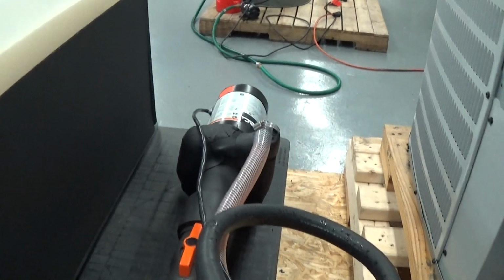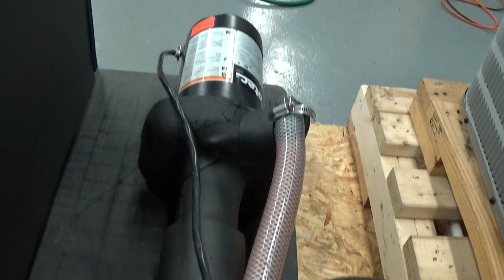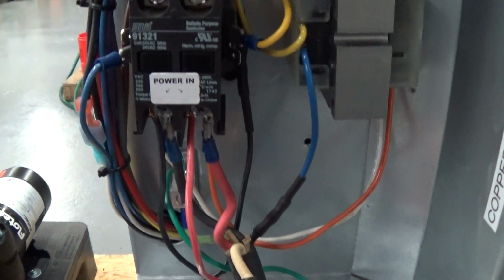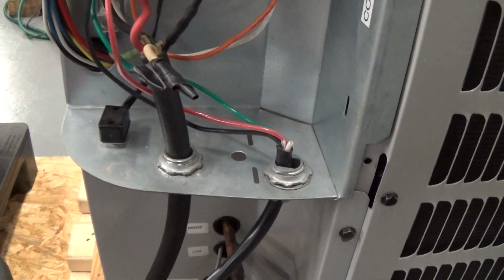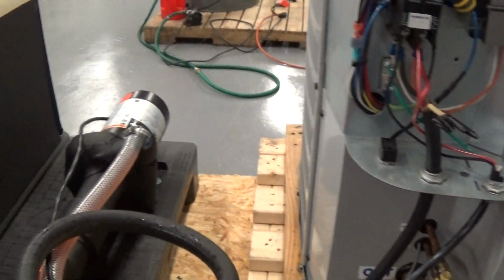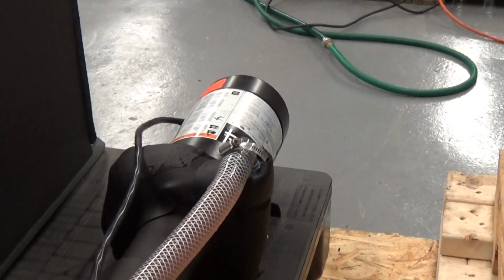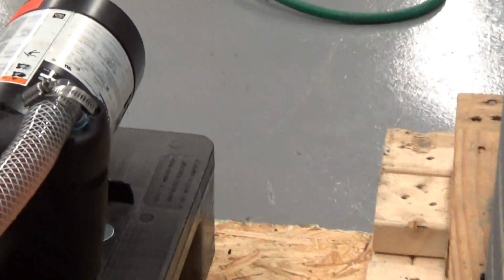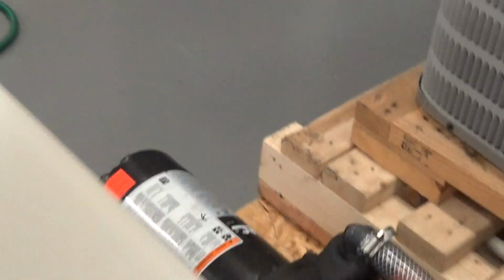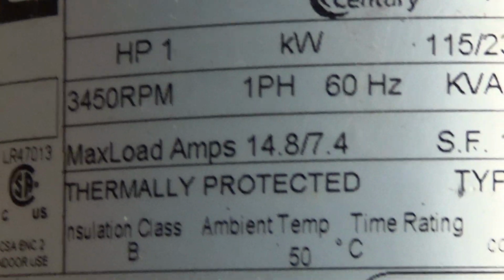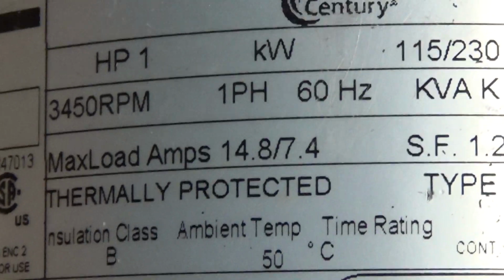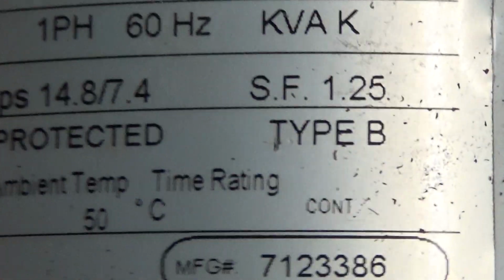The chiller is wired for 208, 230 volt single phase power. In our test environment here, we actually just wired it right back to the main power in here. You can do that too. If you do, just make note of the amp ratings on the pump, which is like 7 amps and change when it is running. Let's double check that is the case. Yeah, so the 14.8 amps, that's if it was set up for 115. This will go about 7.4 amps at its 208, 230 single phase.